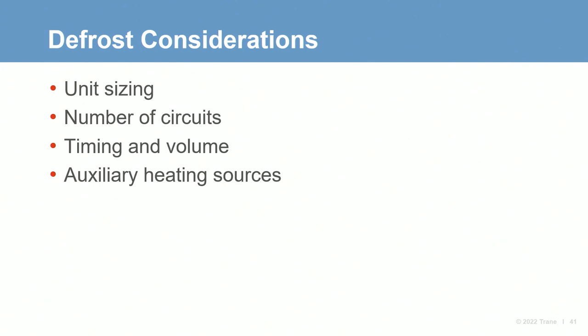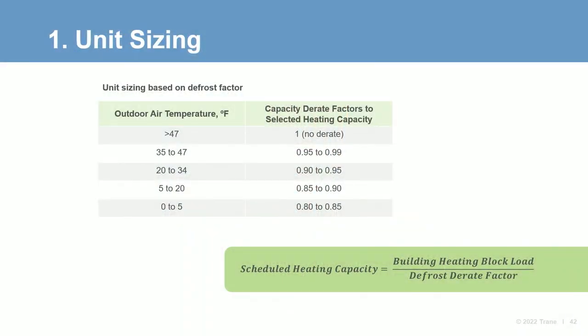So what can be done to address the impact of defrost? We discussed several items and unit design considerations on this topic in our recent ENL on decarb, but they are worth reviewing here as well. Let's review this list. The first is unit sizing based on a defrost derate factor. Defrost operation results in a weighted performance derate to the equipment heating capacity delivered. Some judgment is involved by the designer because the frequency and therefore impact of defrost operation is dependent on actual operating conditions. In an effort to simplify the impact of defrost on unit sizing, we have developed a derate factor.